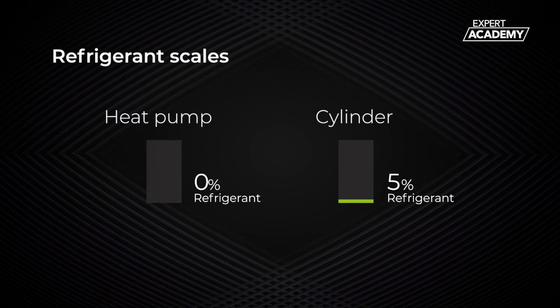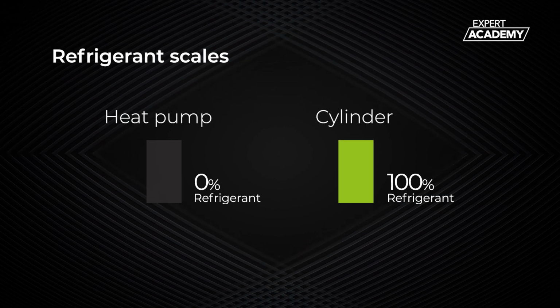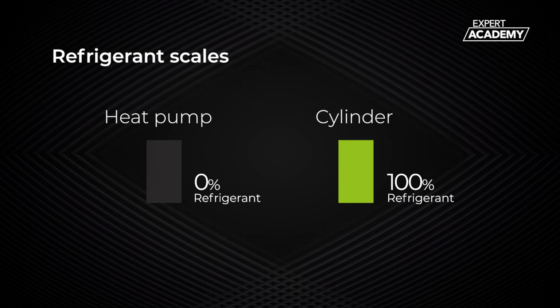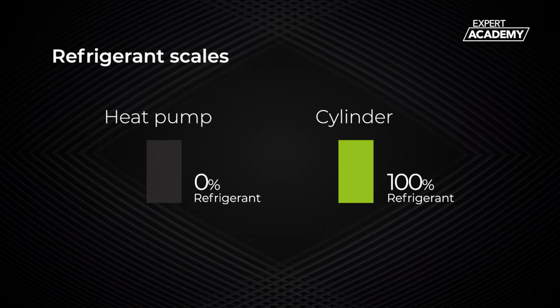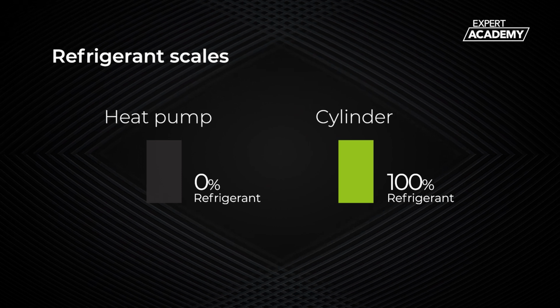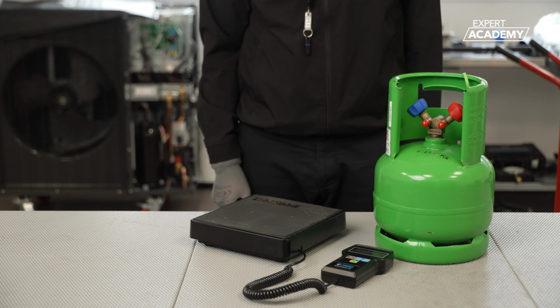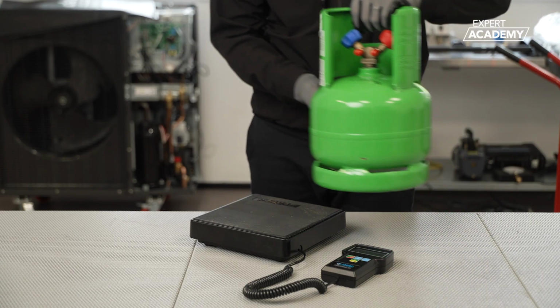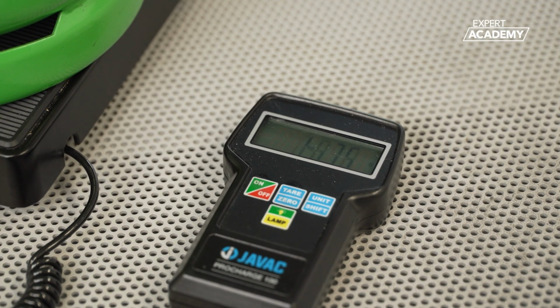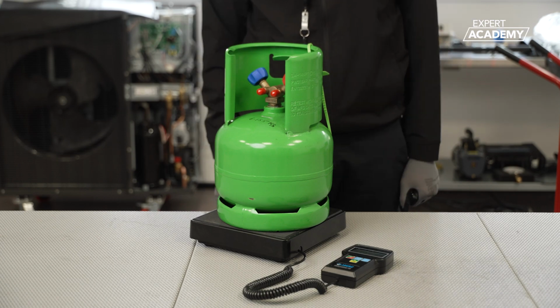The recovery machine pulls the refrigerant out from the heat pump and transfers it into a cylinder where it would be safely stored until it is ready to be reintroduced back into the heat pump. A set of scales is used to weigh the refrigerant bottle, allowing us to measure how much refrigerant has been removed from or introduced into a circuit.